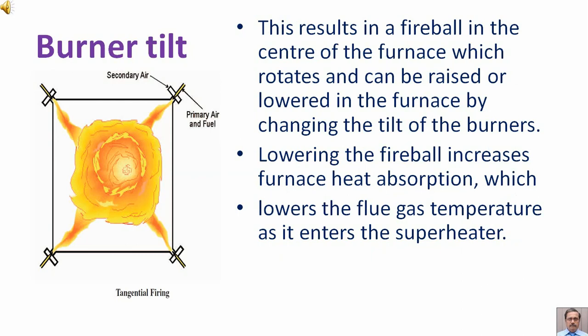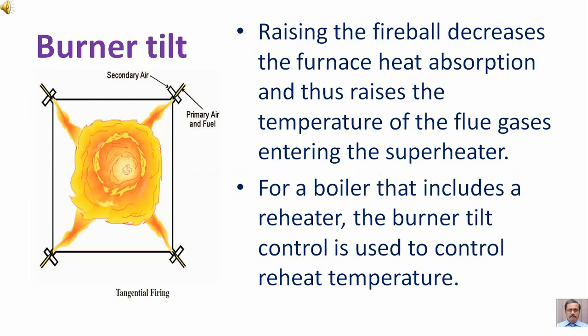This results in a fireball in the center of the furnace which rotates and can be raised or lowered by changing the tilt of the burners. Lowering the fireball increases furnace heat absorption, which lowers the flue gas temperature as it enters the superheater. Raising the fireball decreases furnace heat absorption and thus raises the temperature of the flue gases entering the superheater.